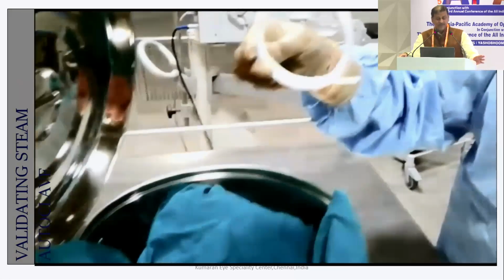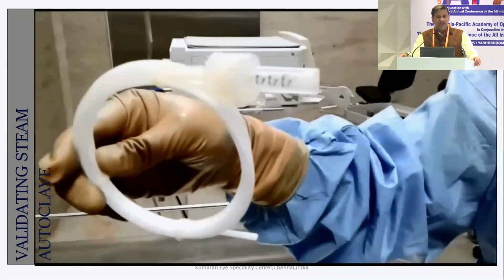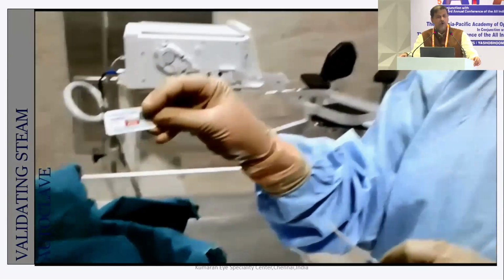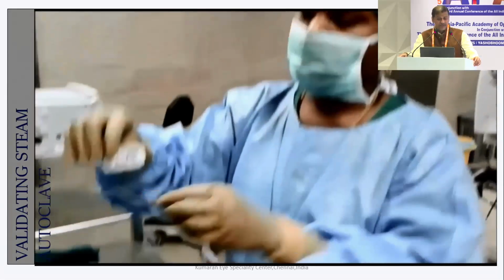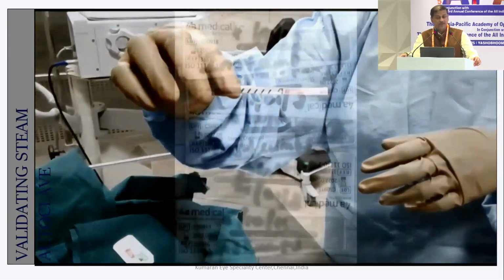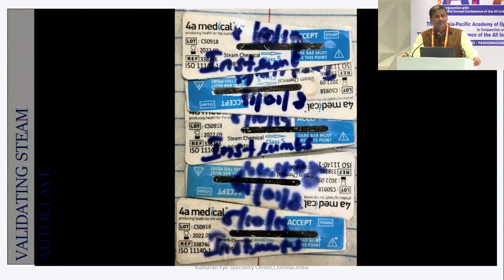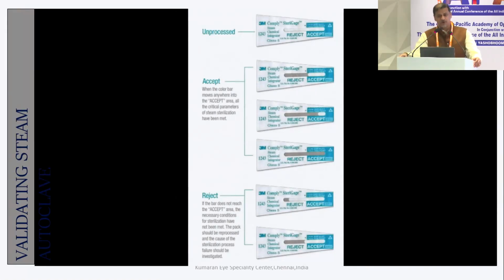Once the autoclave is open, always teach your paramedical staff to first inspect all the indicators to ensure that the proper color change has happened. So here you could see the paramedical staff visually inspecting all the validating indicators. As a surgeon, it is your duty to always have a look at all these indicators before you start your surgery, because if the staff education is not proper, then they could miss a failure. So always follow the manufacturer guidelines telling you what is a clear-cut positive test and what is not.